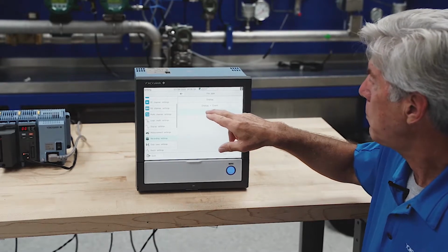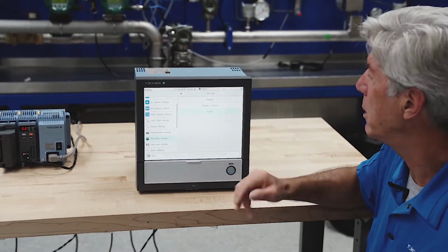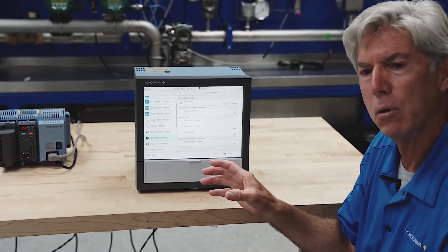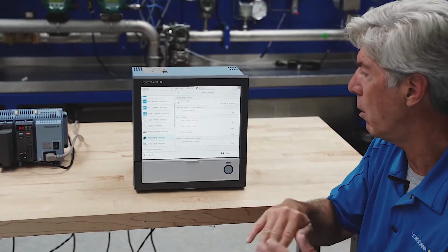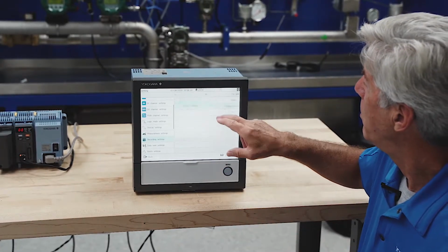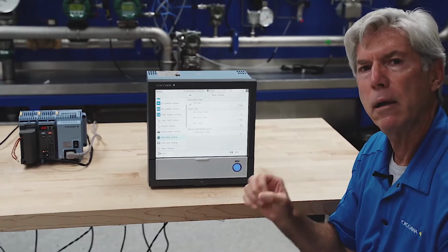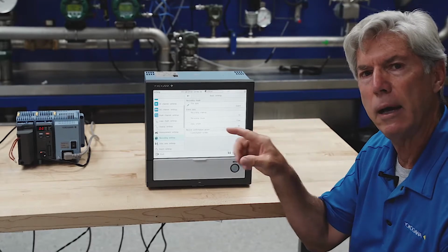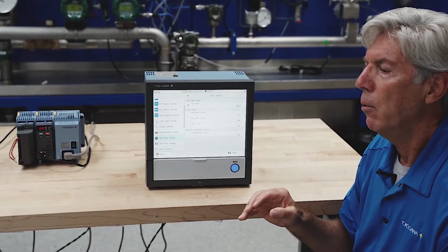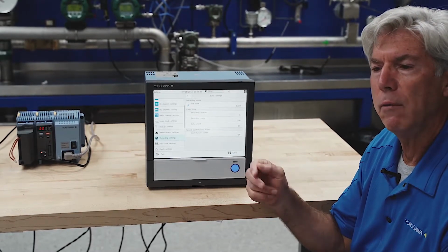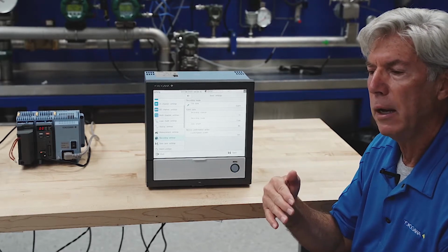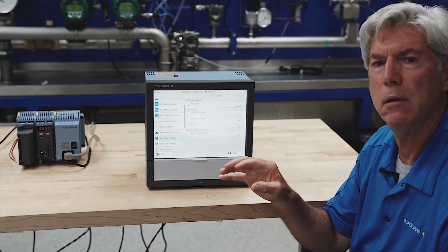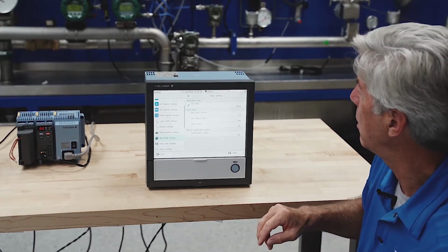Display and event: you can have a display mode being logged, and then you can have an event mode ready to capture data at a much faster log rate in the background if you have an alarm trip point or something like that. Event mode is like the old classic dotting recorder. There was a paper recorder where it would make a dot on a piece of chart paper. If you were logging a value every second, it would ignore the previous 9 values and only log the 10th sample it saw at that 1 second, okay?